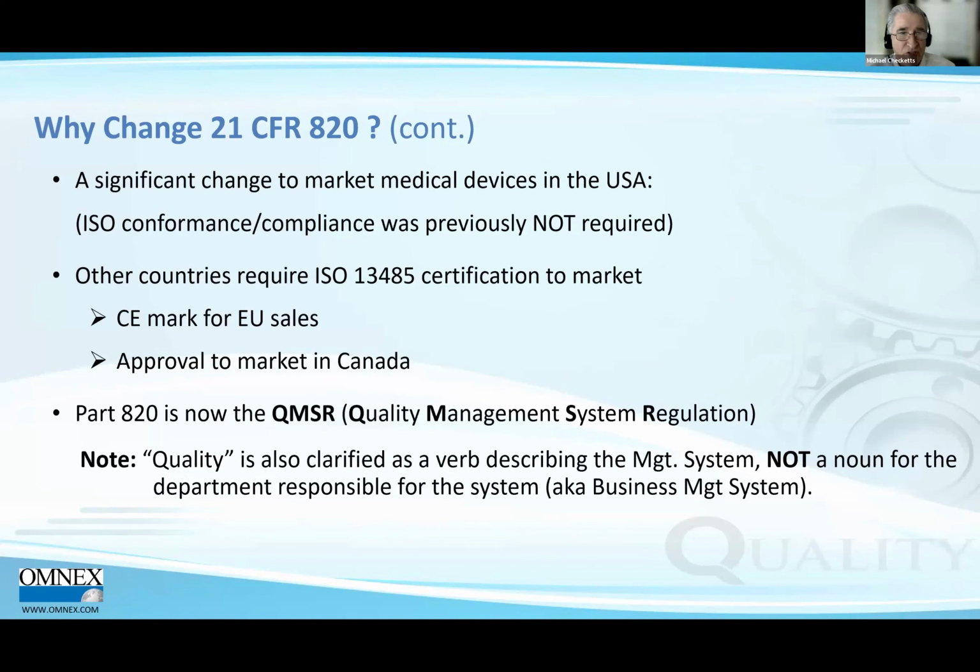Why change 21 CFR? A significant change to the market of medical devices in the US is that ISO conformance or compliance was previously not required. FDA had their own rules. 13485 had their own rules. 13485 is voluntary. FDA rules are not voluntary. So we're eliminating that confusion.